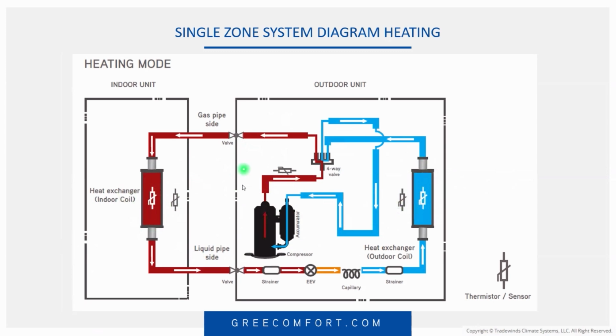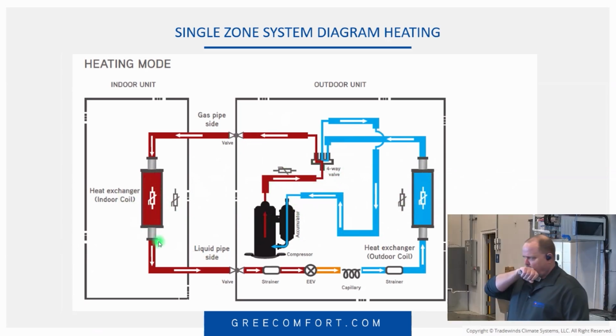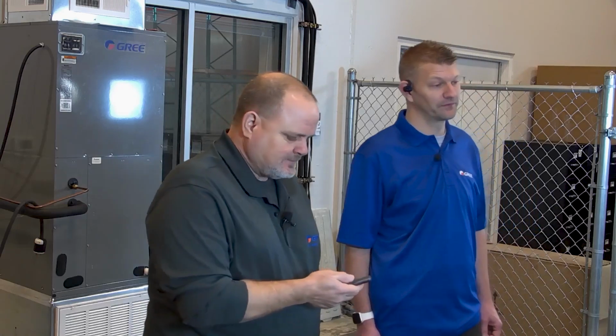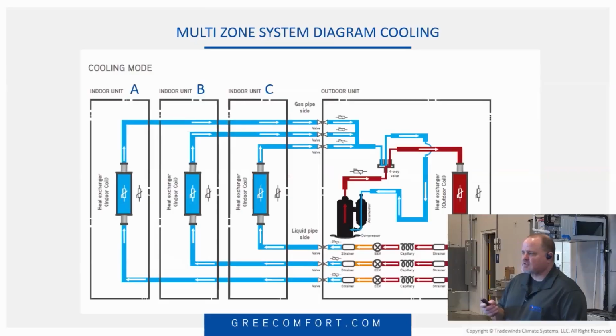Meanwhile, the machine is also protecting itself. It's looking at the discharge temperature of that compressor and making sure the compressor is not getting too hot. If it does, what's going to happen? That compressor speed is going to slow down, which inadvertently is probably going to slow down the outdoor fan speed and the indoor fan speed, because we're running in what I like to call a limp mode. Instead of just shutting down altogether, it's trying to survive, right? All right, so now let's take it one step further.